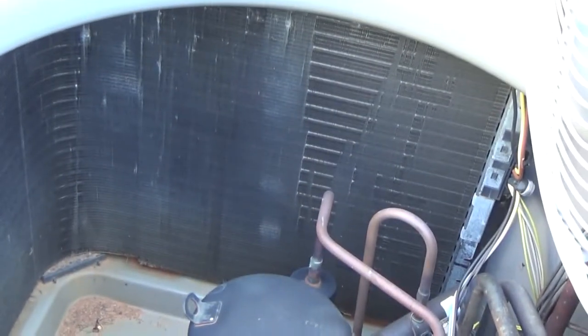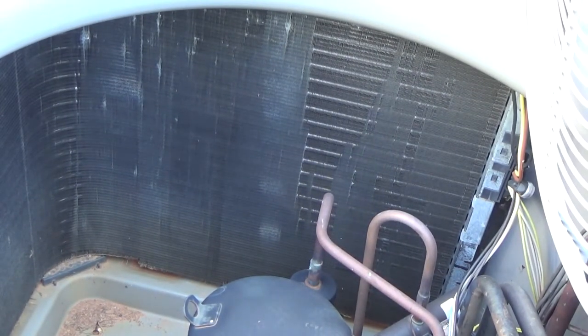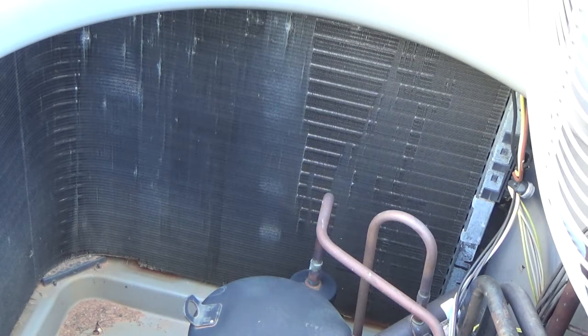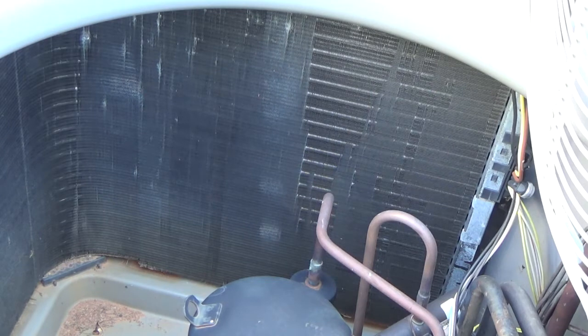Also, I want you to look at the coils. Notice that they're black - the reason is they're painted. So if you get a cleaner that's so harsh it takes the paint off, that paint is going to get in there between the fins and clog them up, reducing your cooling capacity. Then this thing is going crazy because it's not discharging heat into the air.